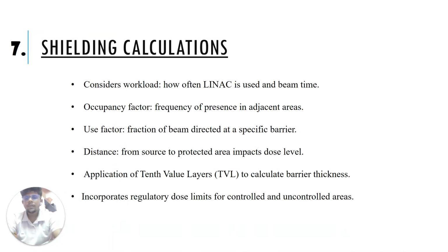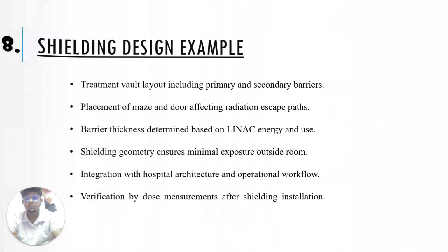Shielding calculations. Shielding calculations consider the workload, occupancy factor, use factor, distance, and application of the tenth value layer (TVL) to calculate the barrier thickness. They incorporate the regulatory dose limits for the controlled and uncontrolled areas.